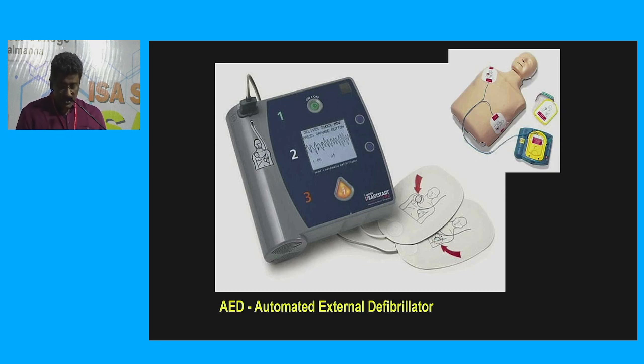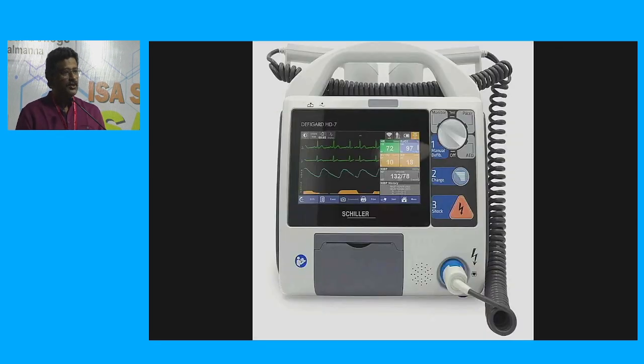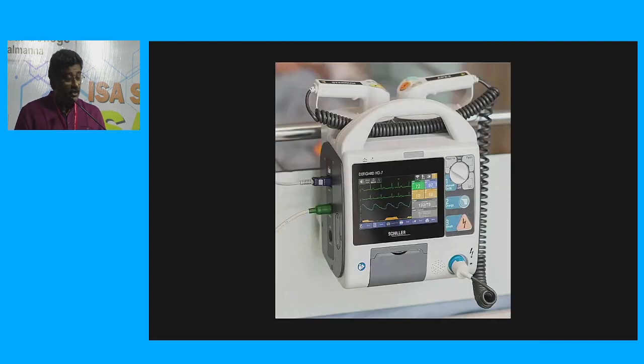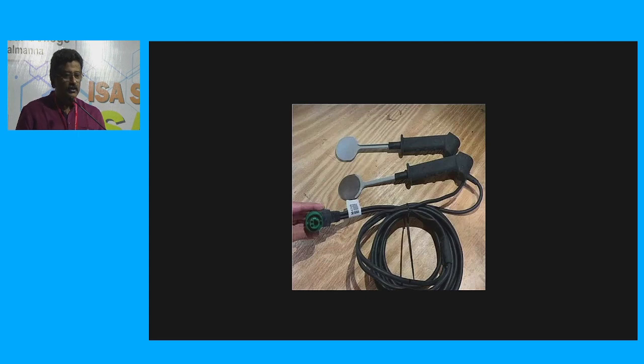The present defibrillators have all these incorporated into them. If you turn to one side, it becomes the manual one. If you turn to the opposite side, what you see on that white part is the AED. It also has a provision for transcutaneous pacing. So everything is included in these machines. It can be portable, you can see it is kept on each cot. And that is the internal defibrillator.